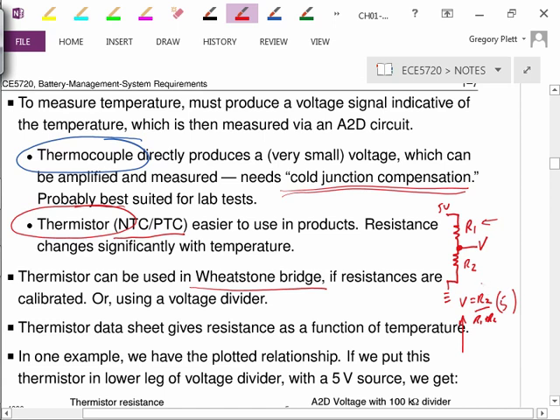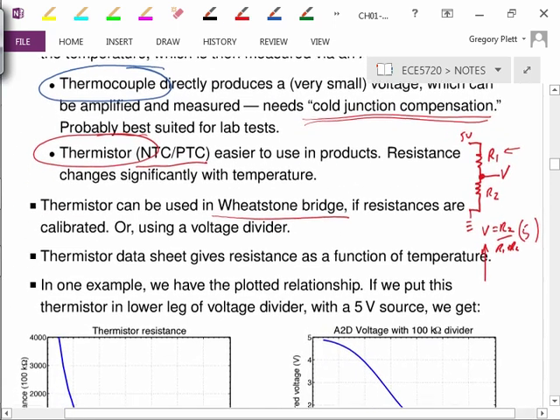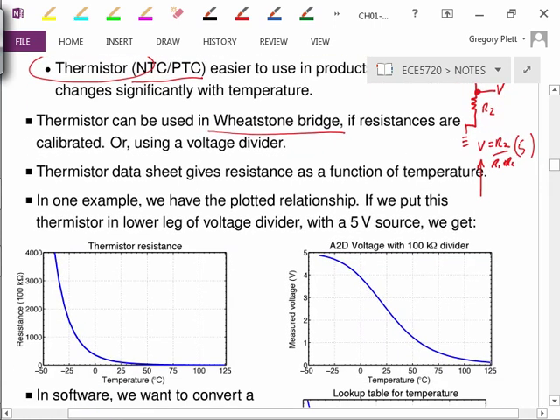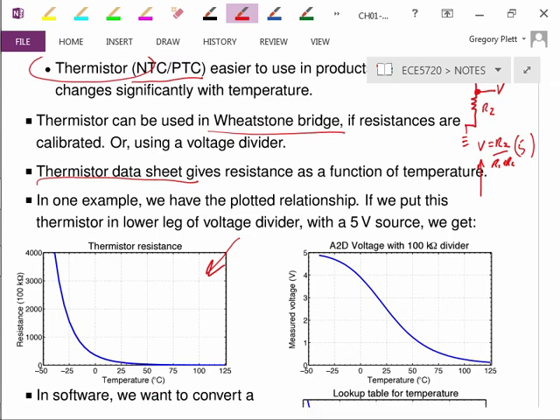From thermistor resistance, I infer temperature. Once I know the resistance, I go to the thermistor data sheet, which gives me a table or function that plots resistance as a function of temperature. Here's an example from a data sheet of thermistor resistance versus temperature, with temperature in degrees Celsius on the bottom axis from minus 50 up to 100 degrees Celsius, and resistance in 100 kiloohms on the left axis, going from essentially 0 up to lots and lots.